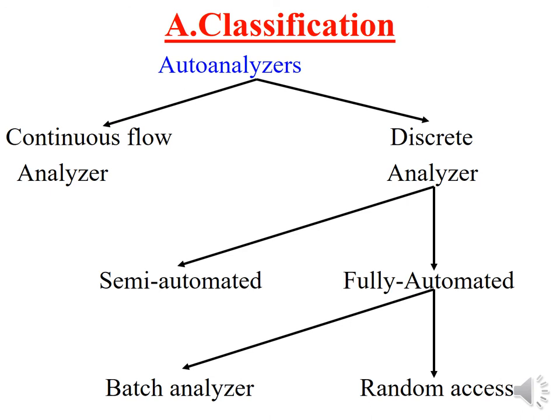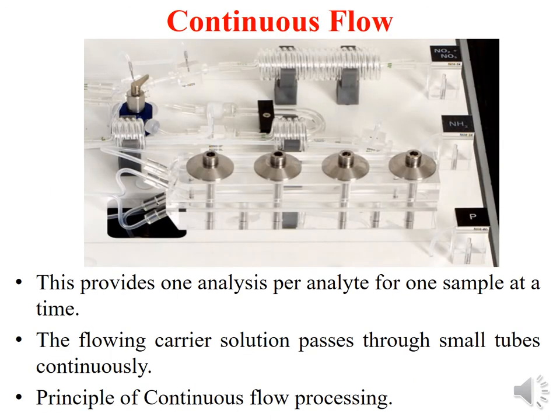Let us see what a continuous flow analyzer is. It provides one analysis per analyte for one sample at a time, which means multiple tests cannot be carried out with one sample — only one test can be performed with one sample at a time.